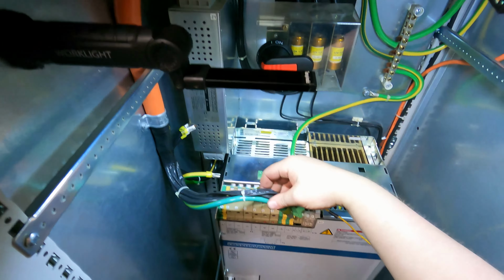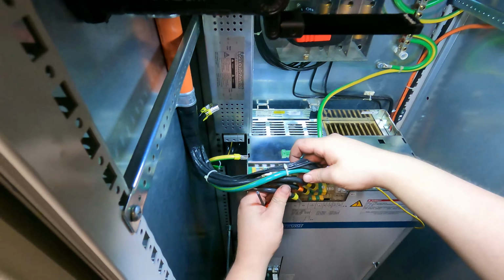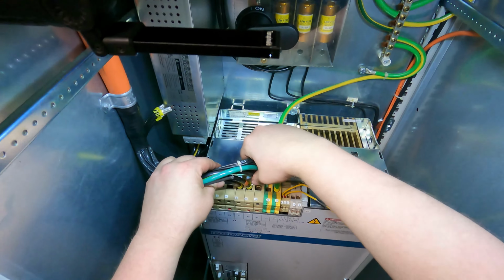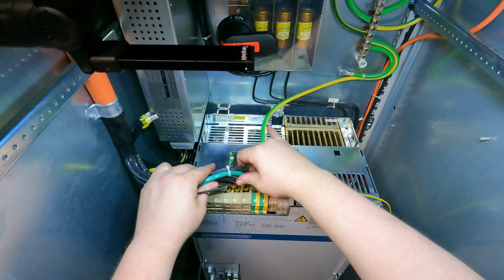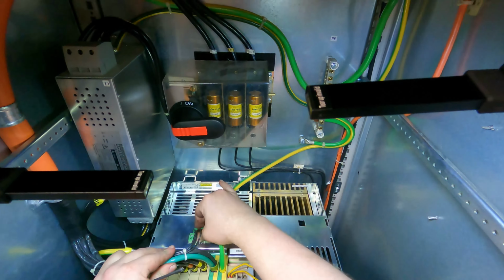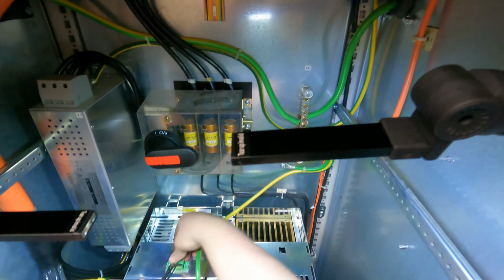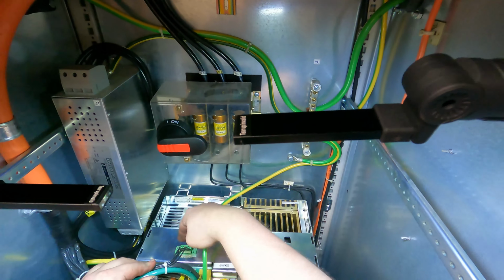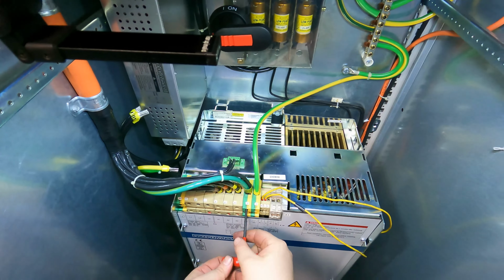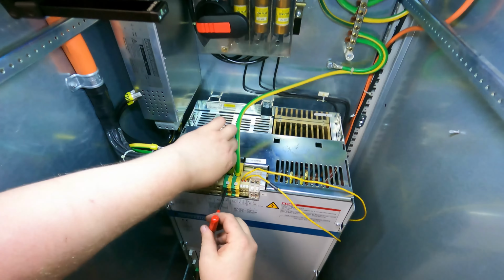Okay. Alright, and this is the motor ground. For 480, it's brown, orange, yellow. Get them all stuffed in first. You can plug this one in the back. You want to make sure that that one's seated well, and it can mess you up if it is not properly seated.